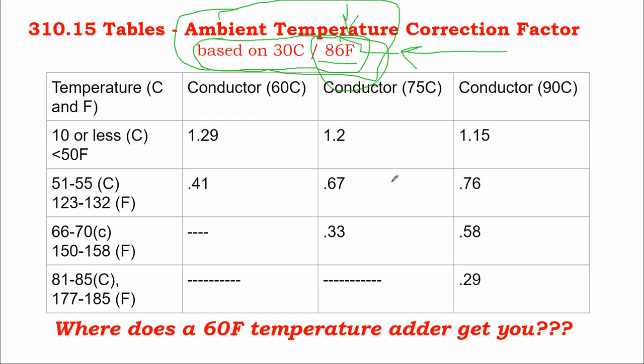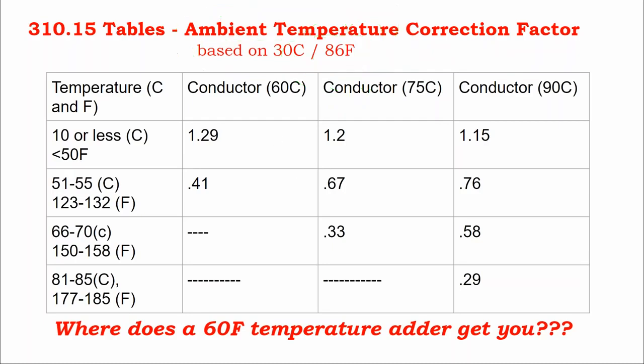It's, to me, kind of confusing that they have these different charts, because you'll get to the same point whether you use all the 86 degree Fahrenheit temperature charts or you use all the 104 degree Fahrenheit temperature charts. The end result, the end sizing calculation, will be exactly the same. Anyway, we'll get into that in a minute. How do you read this chart?